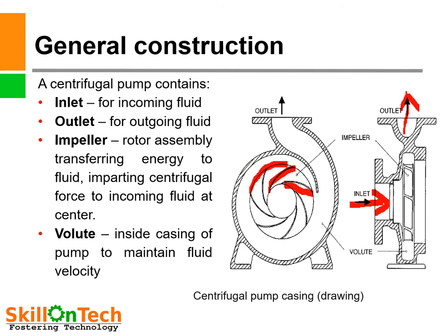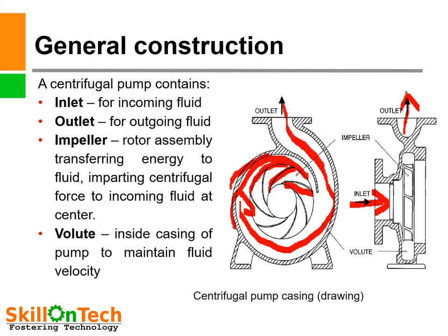This rotor assembly transfers energy to fluid, imparting centrifugal force to incoming fluid at the center. Here you can see this is a volute casing — the area of the volute casing is increasing. This area is getting increased, so this converts the kinetic energy of liquid into pressure energy at the discharge. If you install a pressure gauge at the discharge nozzle of the pump, you can see what is the manometric head developed by a centrifugal pump. This complete action is due to centrifugal force generated by an impeller.